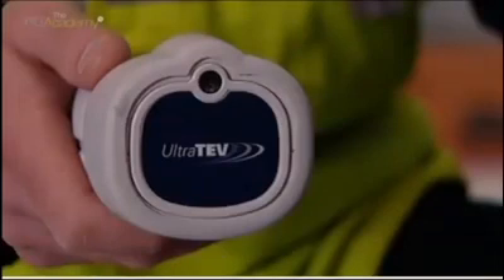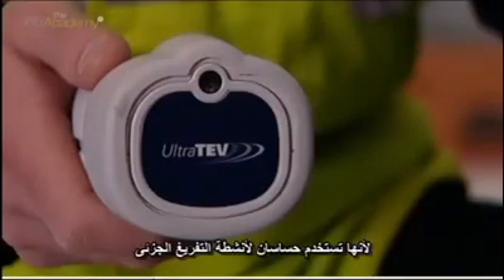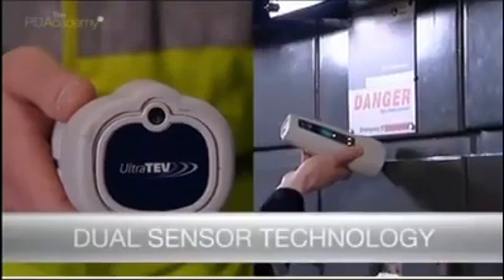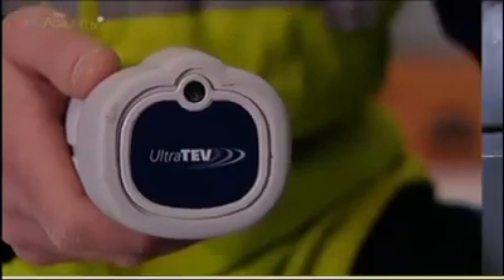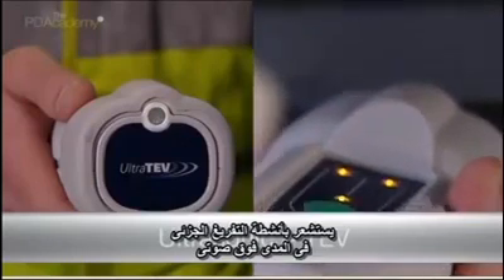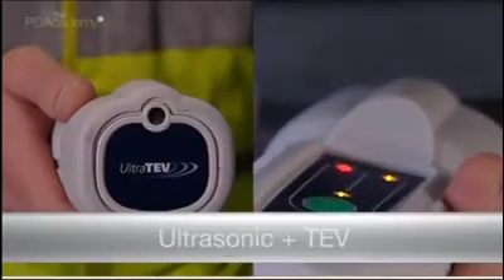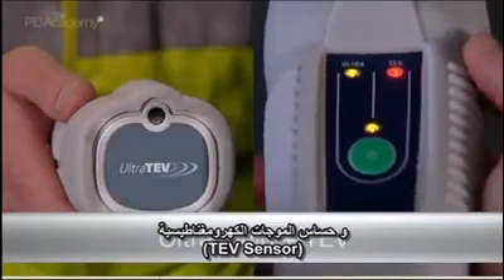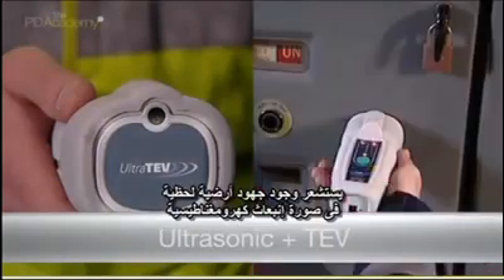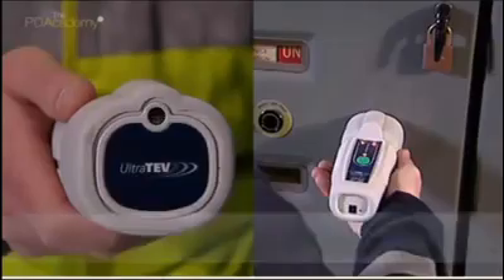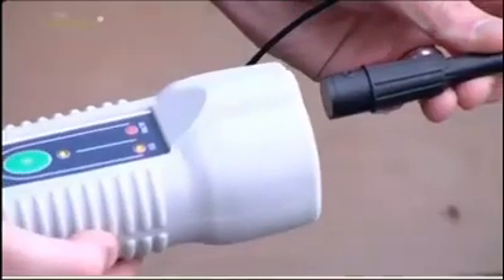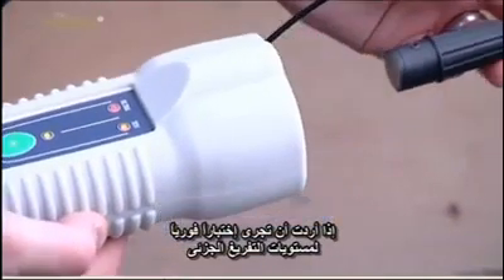This instrument is accurate because it uses two PD sensors. The ultrasonic sensor listens for PD activity in the ultrasonic range. And the TEV sensor checks for transient earth voltage effects in the form of radio energy emissions. So if you want an immediate check for critical PD activity, this is the perfect type of instrument.